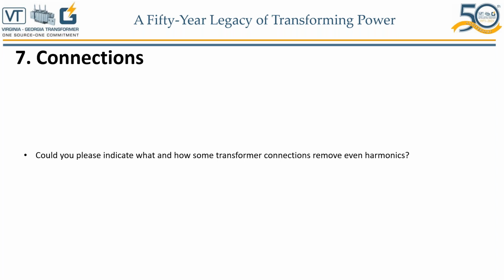But what we also do, just because we are transformer people, is that when you tell us the harmonics this transformer is going to operate with, we consider the increase in the losses in the windings, and then we recommend to derate it or design it with higher MVA, and we pay attention to the winding rise calculations. We also give additional clearances to overcome the increase in stray losses. Because as I said, when the harmonics distort the voltage and the current waveforms, it will act like it's increasing the voltage and sometimes even the current inside the transformer.